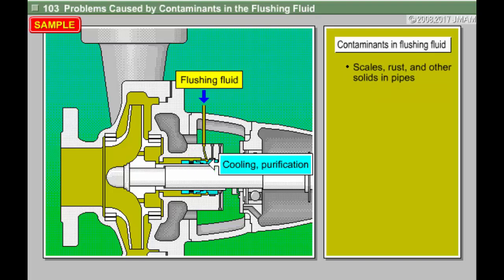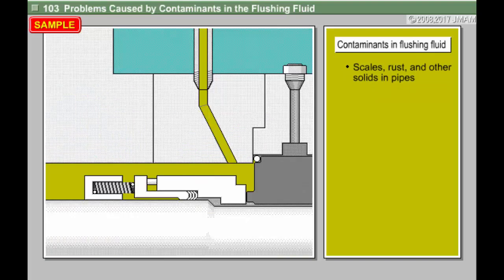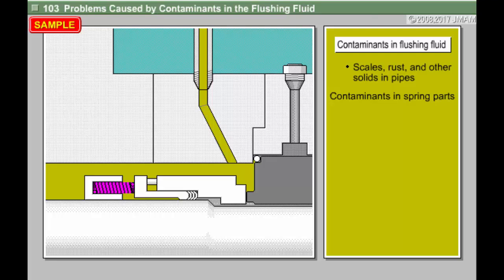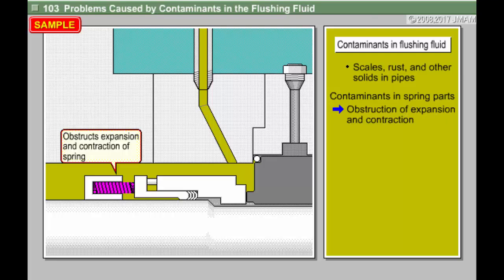A mechanical seal uses the force of a spring to make the rotating ring follow the movement of the shaft in the thrust direction. If sediment accumulates there, it becomes difficult for the spring to expand and contract.